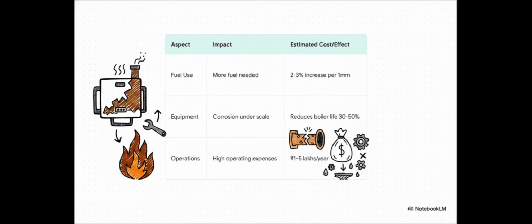For boiler systems, the numbers are just as wild. You actually need more fuel just to maintain your normal output, because that scale acts like insulation. The data estimates a 2 to 3% increase in fuel use per millimeter of scale. So for a mid-size industrial setup, all these headaches combine to create an increased operating expense of 1 to 5 lakhs a year.